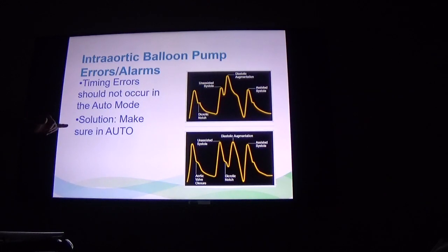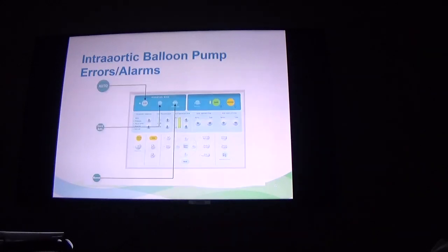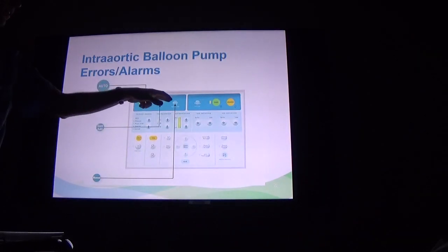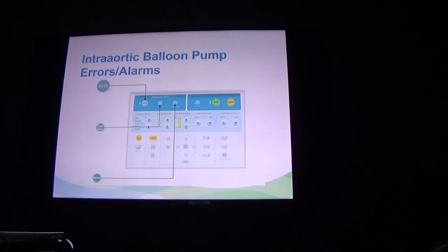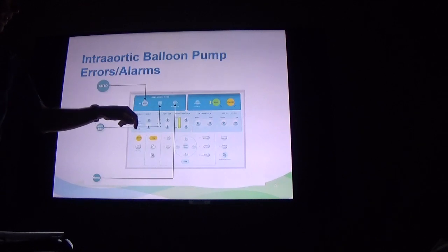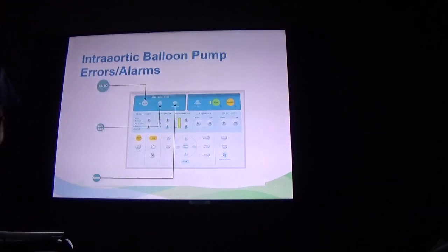So the way we make that ideal is we put the machine in auto mode. So right here, auto mode. Avoid semi-auto and avoid manual, because once you hit semi-auto or manual, you'll have to deal with EKGs, you'll have to figure out your timing of inflation and deflation. It's stuff we don't want to have to deal with. The easiest thing to do is just put it in auto and forget about it, because that will solve most of our problems.